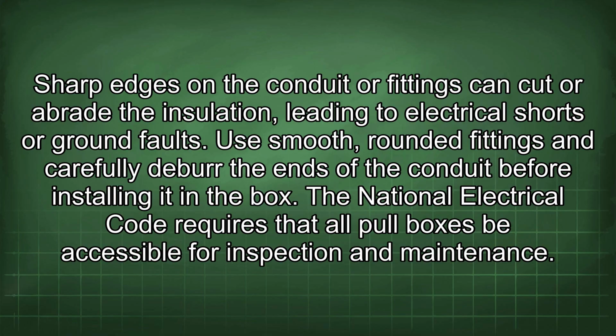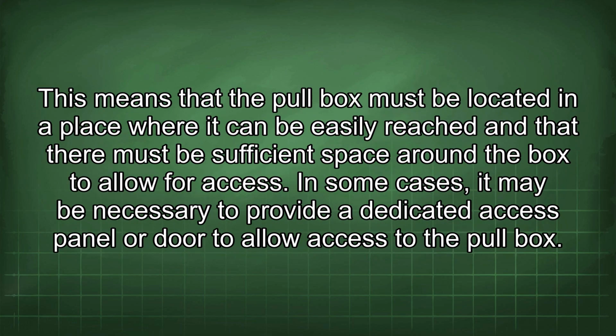The National Electrical Code requires that all pull boxes be accessible for inspection and maintenance. This means that the pull box must be located in a place where it can be easily reached and that there must be sufficient space around the box to allow for access. In some cases, it may be necessary to provide a dedicated access panel or door to allow access to the pull box.